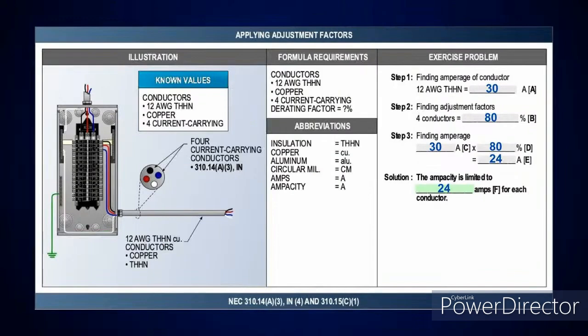But I just like to point these things out because earlier we'd done one, and I was talking about if I calculated a load where the wire size didn't match up with the overcurrent device, and I was given examples. There's another good example of that. Now, this is where we're going to get in. We start looking at adjustment and correction factors.